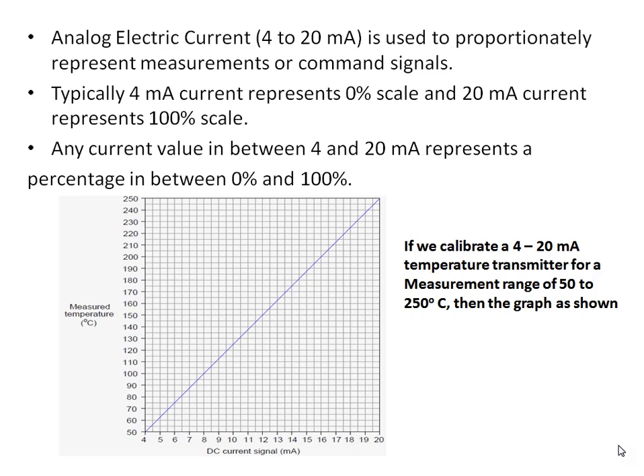Analog electric current of 4 to 20 mA is used to proportionally represent the measurement — whether it is a process variable or command signal and a manipulating variable. Typically, 4 mA current represents 0% scale and 20 mA current represents the 100% scale.